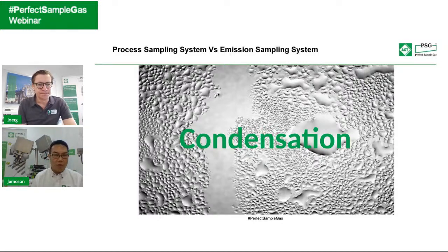Or is it always that the sample we are siphoning or extracting from the emissions application, we call it flue gas, combustion gases, coming from the raw material, depending on what type of raw material. Many times people talk about natural gas, for example, a very clean application. However, what is the most critical part about considering the sampling system for natural gas? That is water. Many people do not realize that natural gas consists of lots of water in the sample. This is something right throughout many experiences.